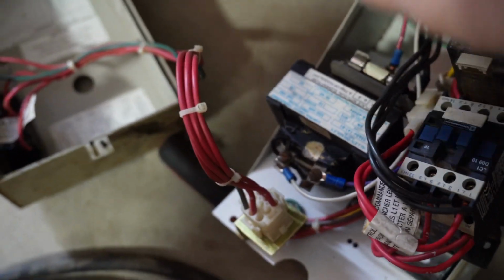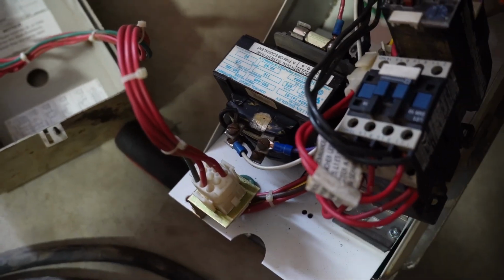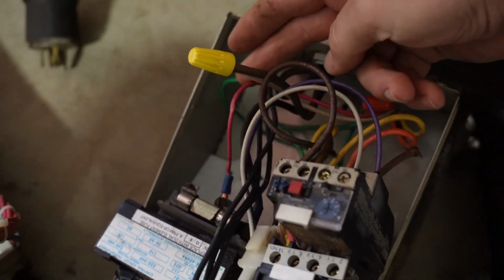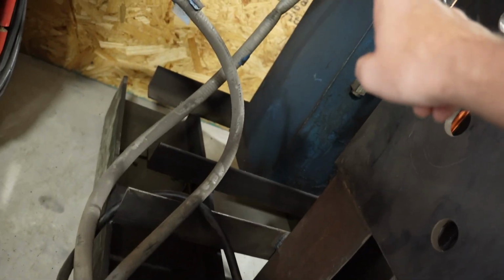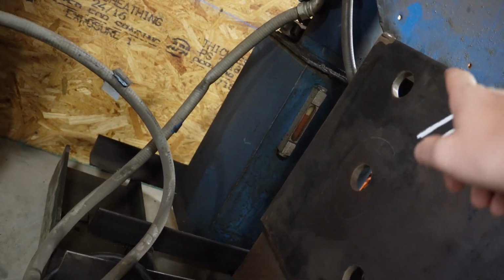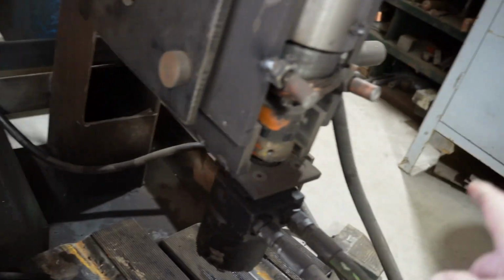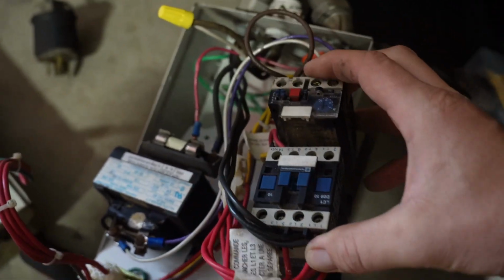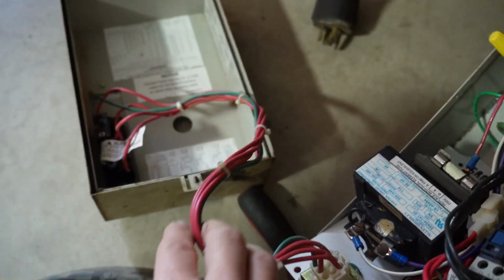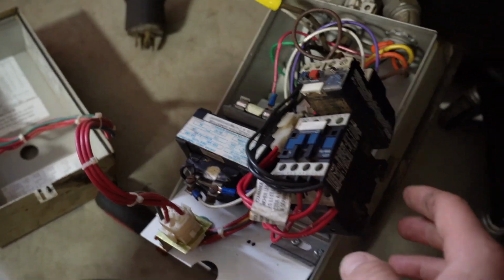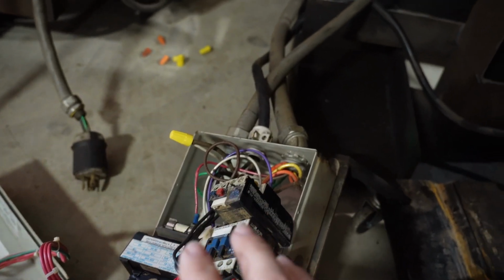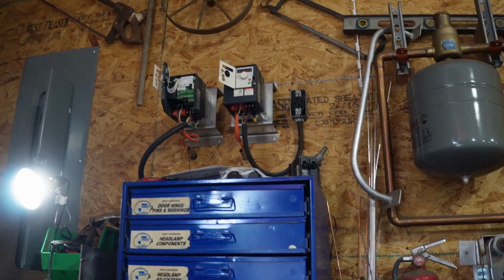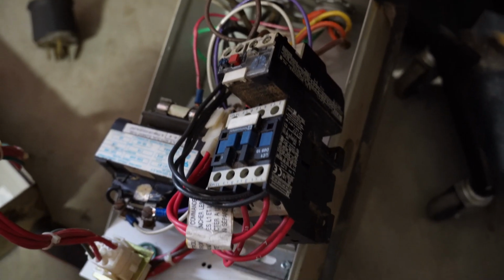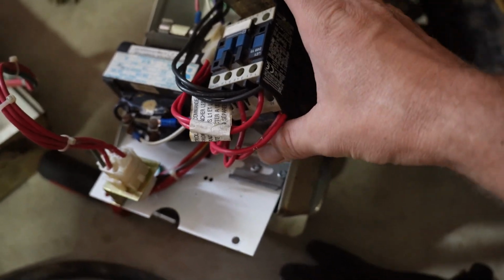That's 2 hots going to the transformer, and then coming out of the transformer, there's a line going up, comes out, goes to our shuttle valve or solenoid valve, comes back through, goes through our foot pedal, comes back out and back into here. So I can delete basically this whole thing and all of this switch mechanism down here, and control the start-stop function of the motor itself with the VFD. I'll program it so it has a slow start, slow stop, like a 2 to 3 second spin up time. That's what I'm gonna do.